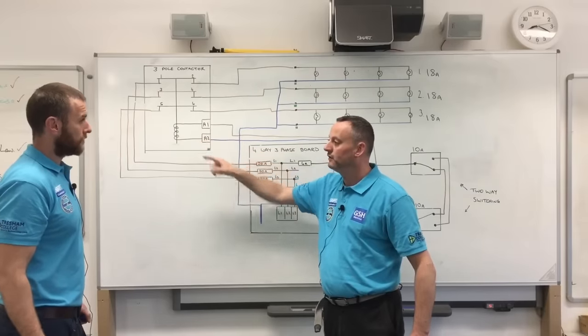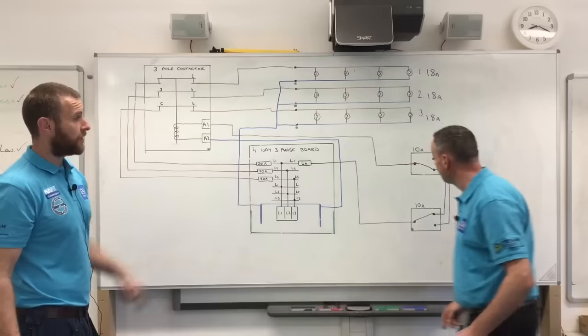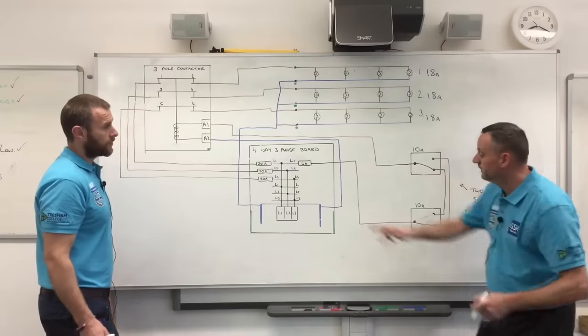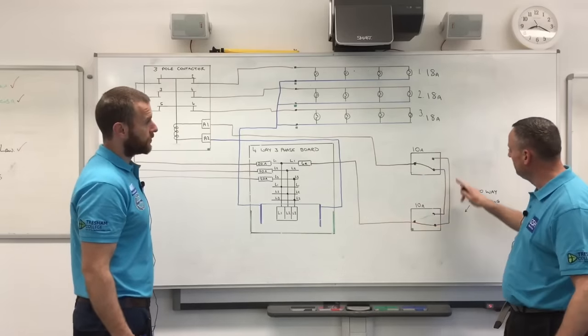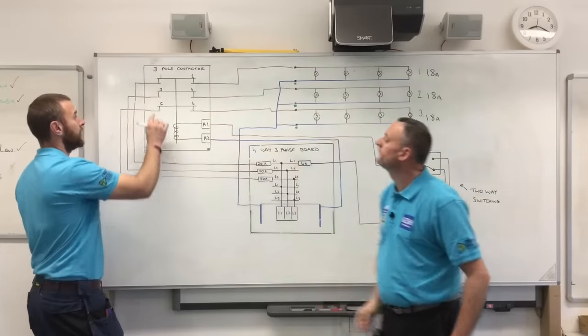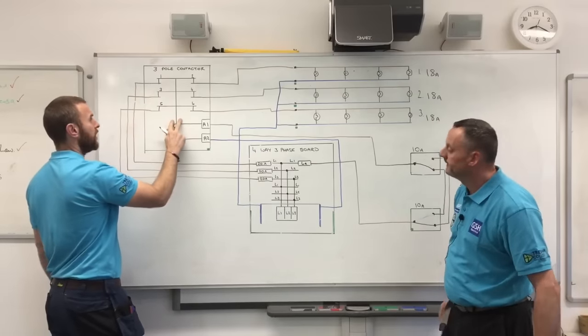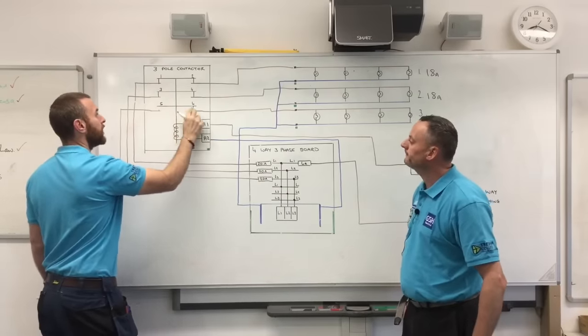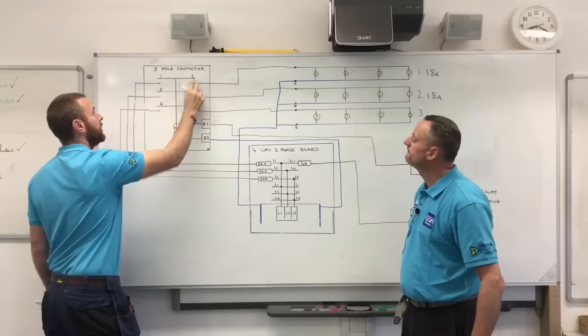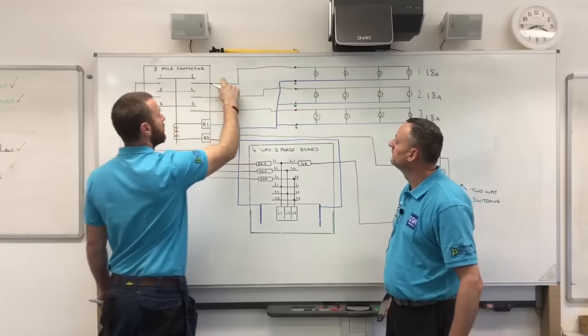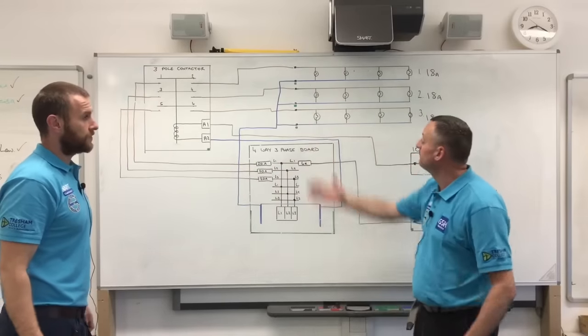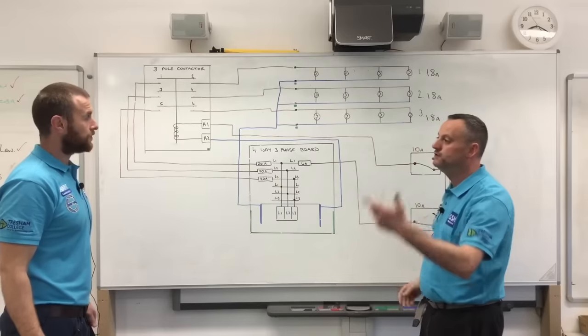Can we just operate the other switch, maybe? So, we did this one. So, we'll take this one back out. Hopefully, we can now see when we draw it through. The line conductor comes to the first switch. It comes through. And now, we've de-energised the coil. So, the coil is now, we haven't got a switch in line there. So, under spring pressure, like Joe explained, the armature springs back. Which breaks these contacts, which opens these contacts. Again, you'll hear a clunk or a click. They come up. They cut the power going through to each light. So, the many lights in a workshop or a warehouse, all the lights have gone off. Simply by turning the switch as you walk out the door and lock it off. Fantastic.